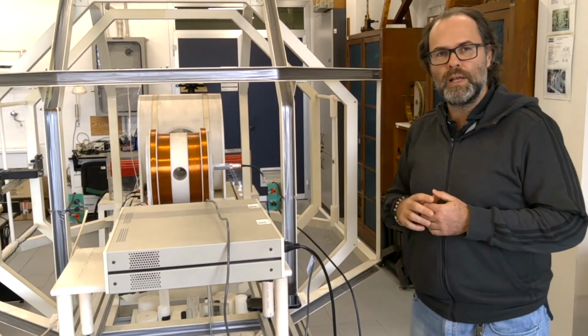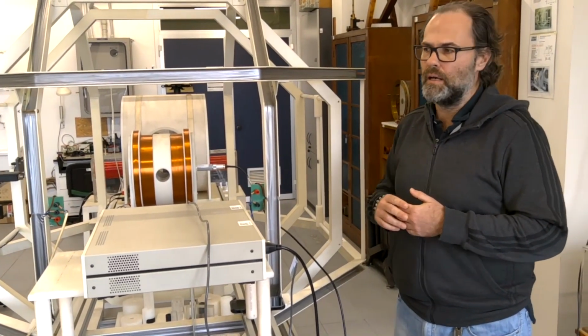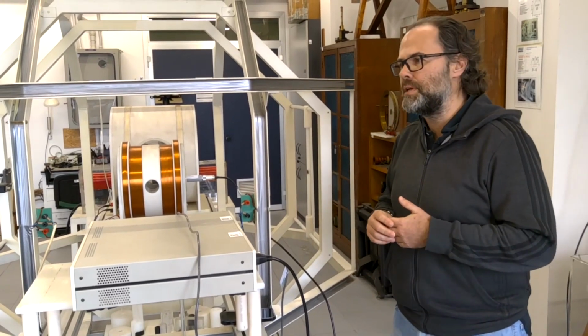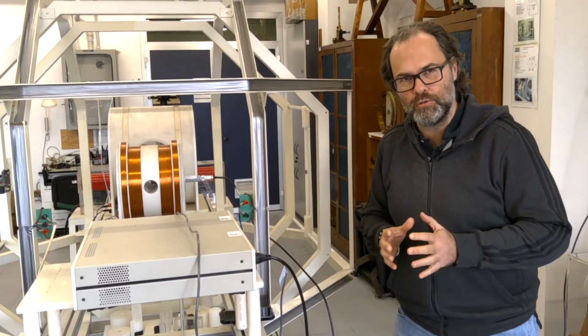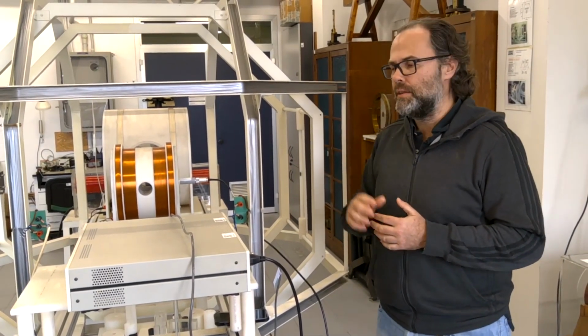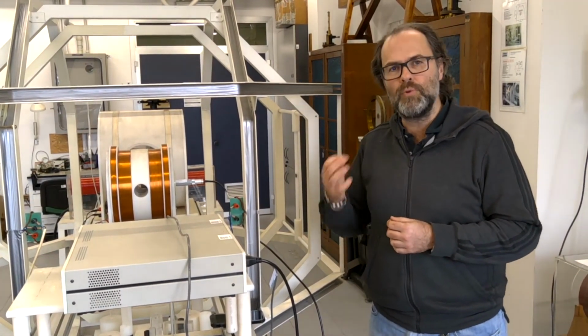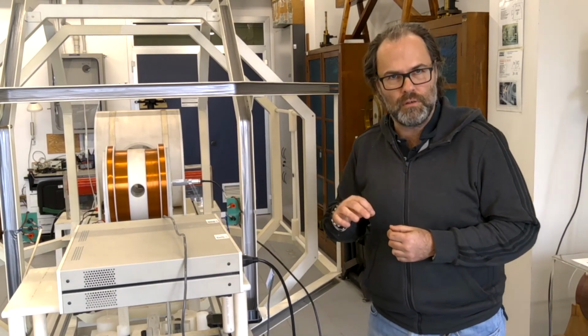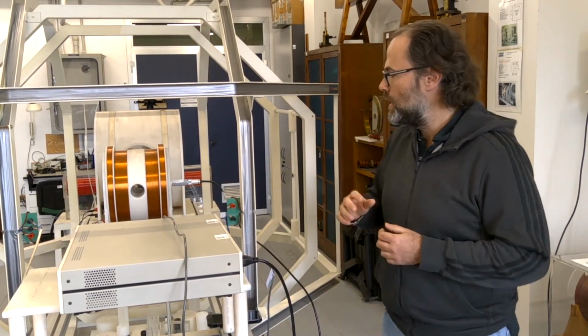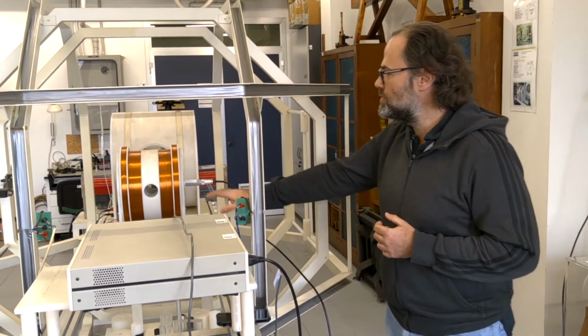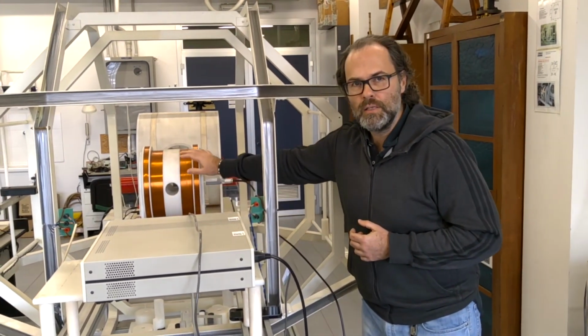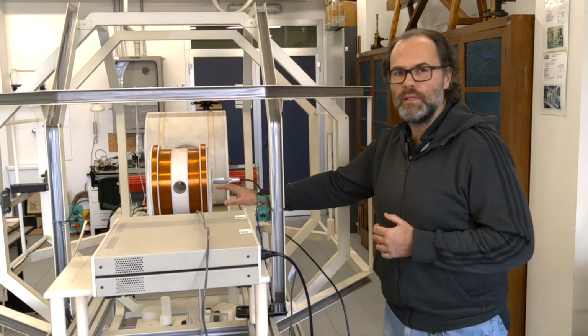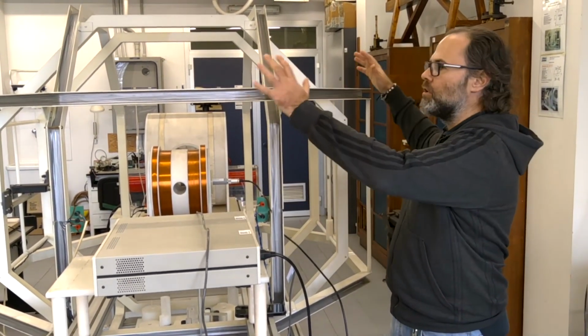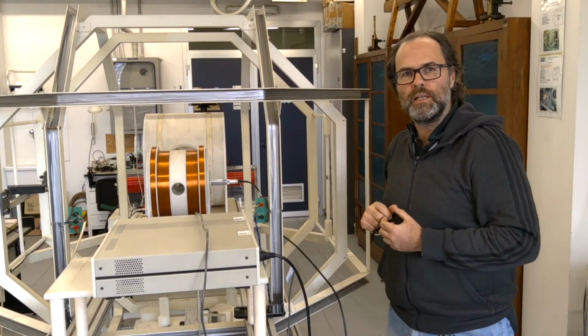The reason why we use a Flux-Gate is that it is a sensor of magnetic field that is extremely sensitive to low values of the magnetic field. But also, a Flux-Gate is a kind of sensor that gives an absolute zero measurement. This means that you do not need to calibrate the Flux-Gate in order to measure the zero. And this is exactly what we want to do. So the Flux-Gate probe is inserted into the transfer coils, and all of this equipment is in the middle of the Helmholtz coils that will be used to compensate for the Earth magnetic field.